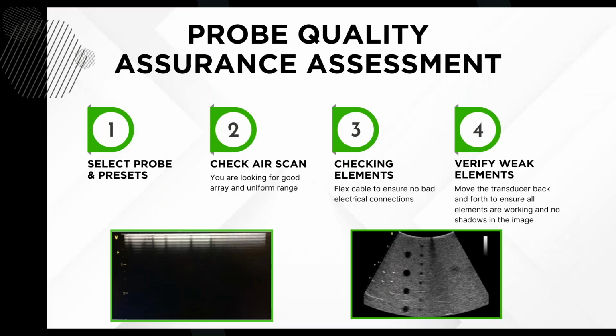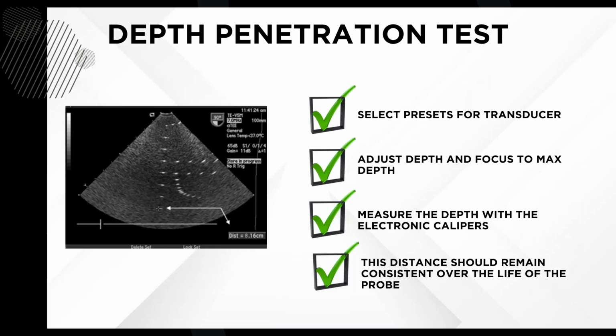So we selected the probe, went over the air scan, checked elements, verified weak elements, depth of penetration. We selected presets for the transducers. We adjusted the depth and focus to the max depth. We measured the depth with the electronic calipers. The distance should remain the consistency over the lifetime of the probe. That's the depth of penetration test.